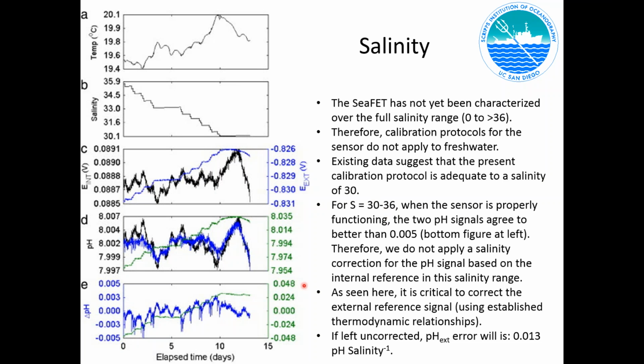We've always known that we have to apply a salinity correction to the pH based on the external reference electrode. And you can see, for example, if you look at this green line in the bottom, this would be the deviation in the pH value in the external reference electrode-based pH if you don't salinity correct it. So these are huge, huge errors for CCAN folks trying to characterize saturation state. These would be unacceptable errors. So if you do apply the understood salinity correction, you get agreement within, when everything's working, the 2 sensors in a SeaFET agree to better than 0.005.